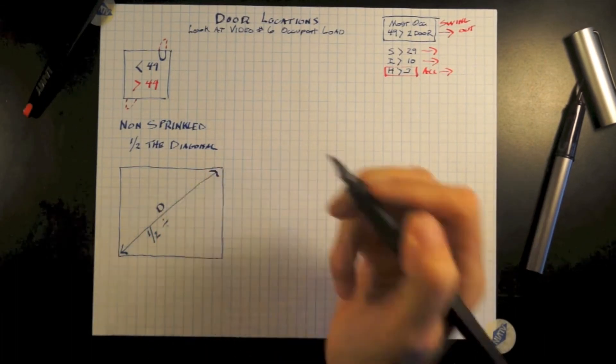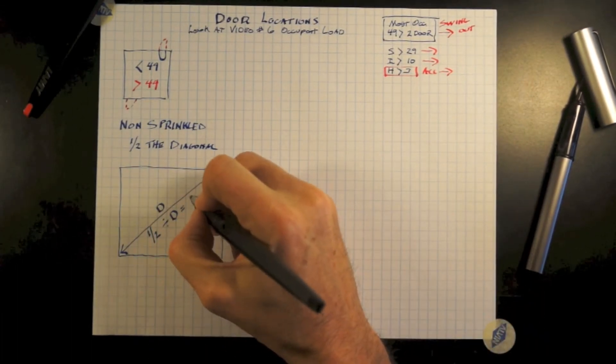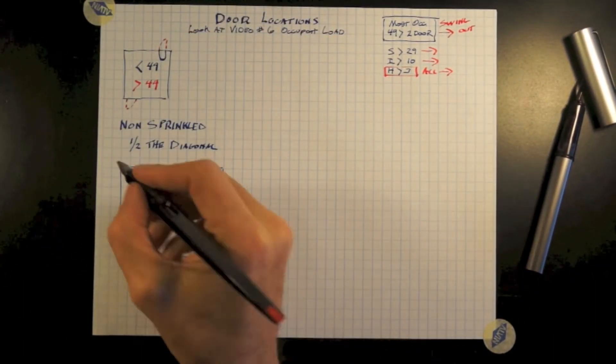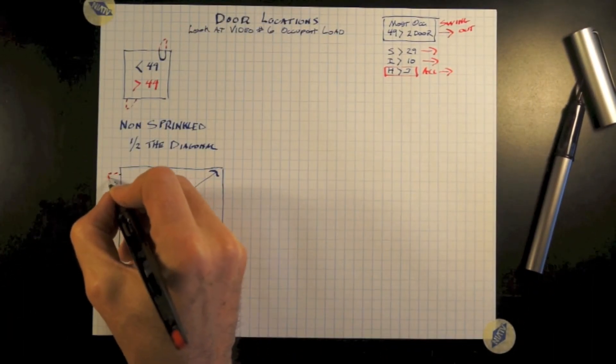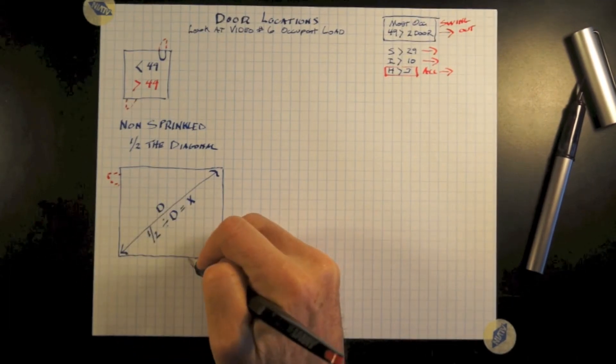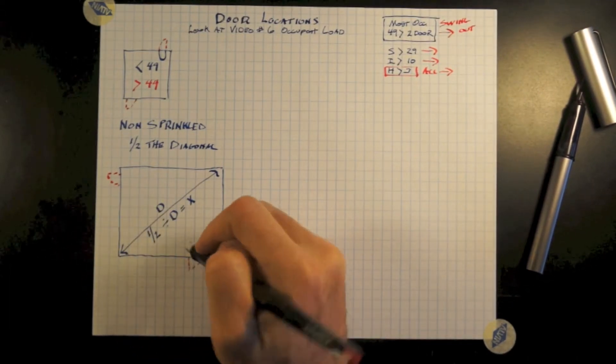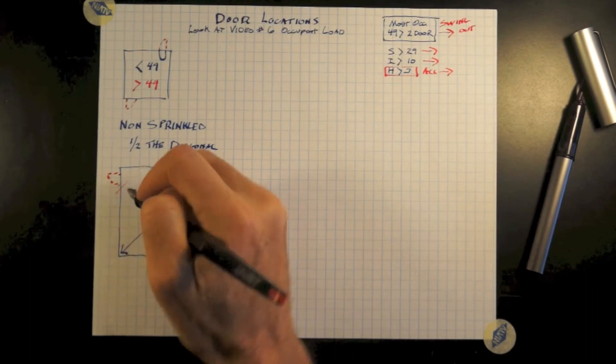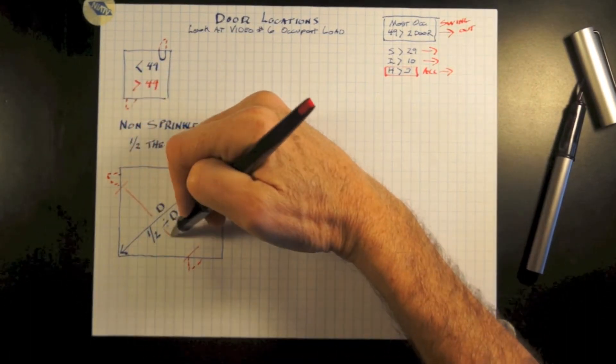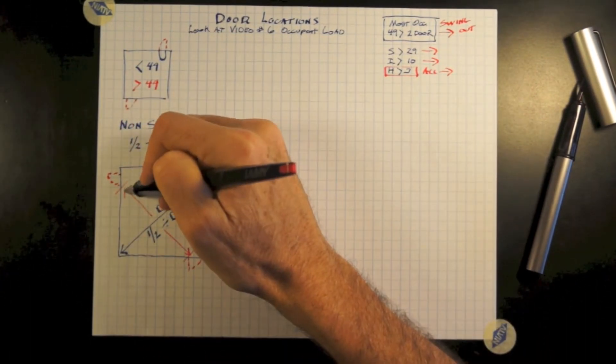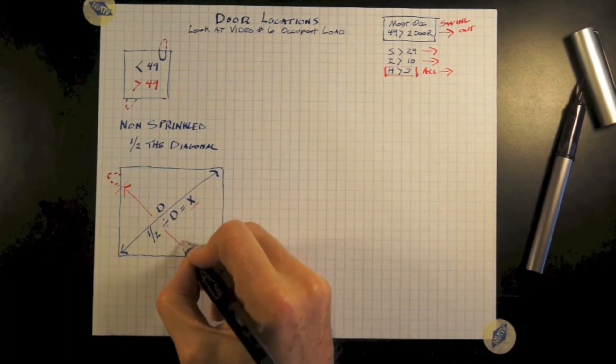So D being the diagonal, one half the diagonal distance equals X. So therefore, our two doors exiting out of the space with the doors swinging in the direction of travel shall not be less than one half the diagonal distance or in other words, X.